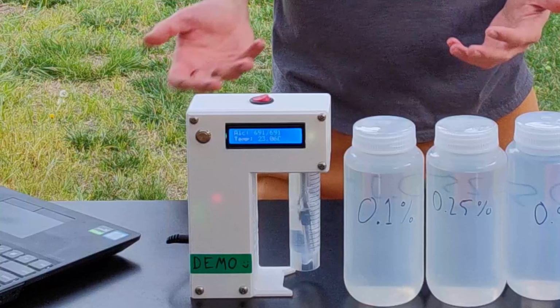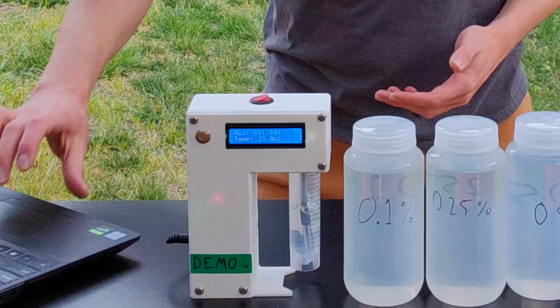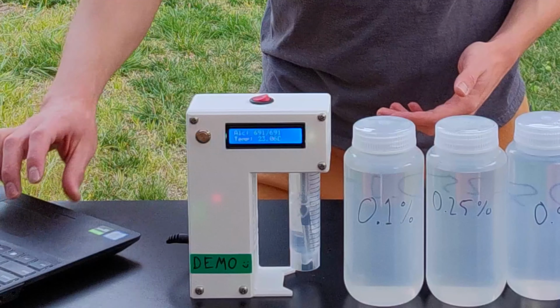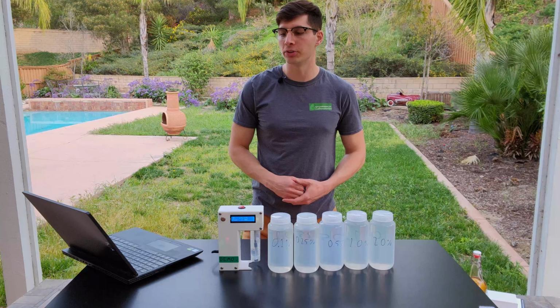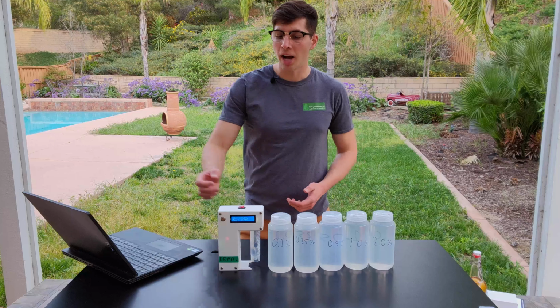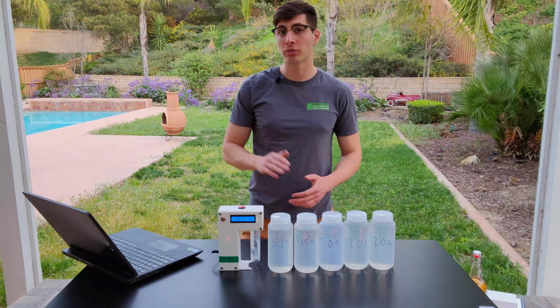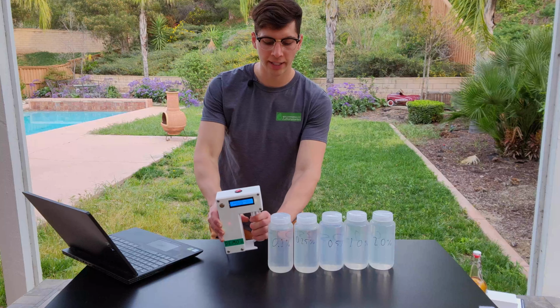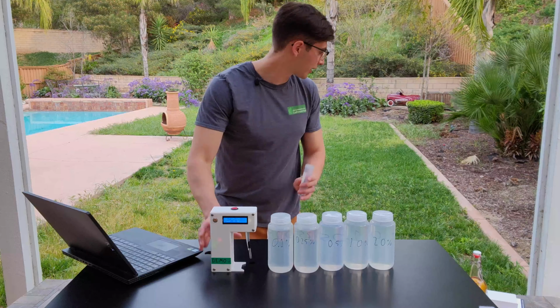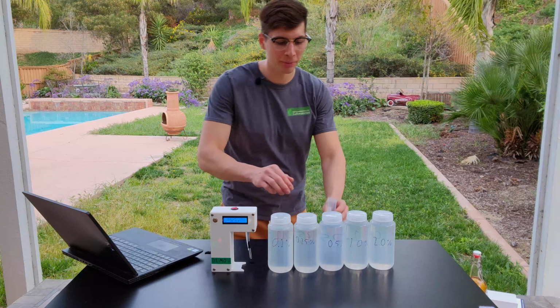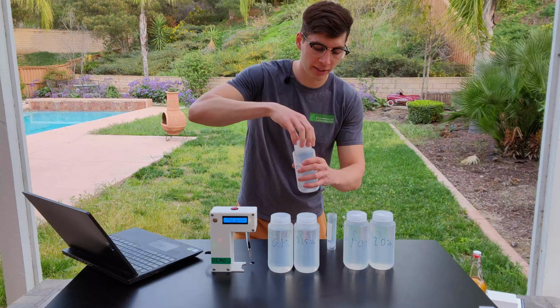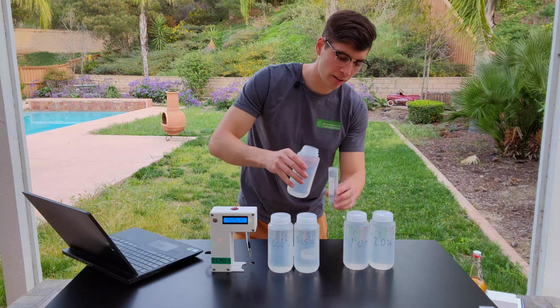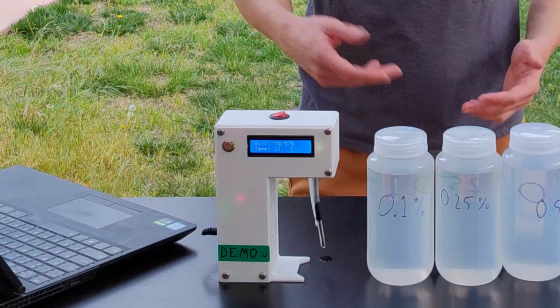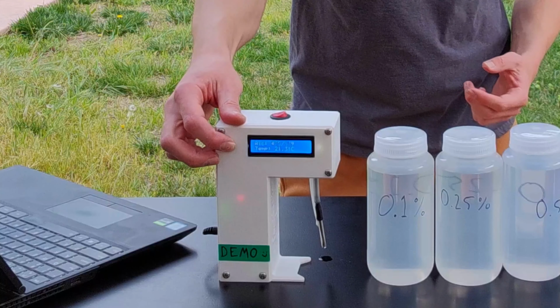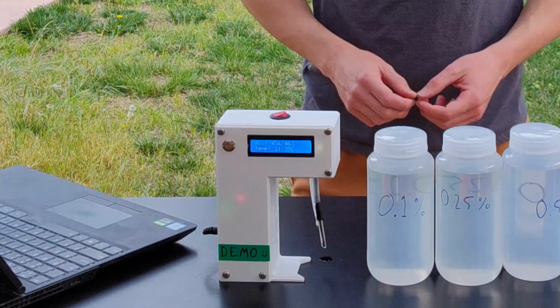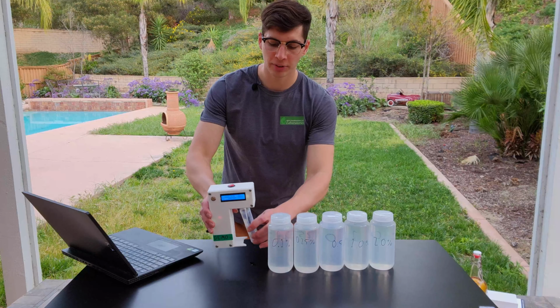So the readings seem pretty stable at about 690, so I'm going to enter that value into the Excel document in the position of the 0.25% alcohol percentage. I've also recorded the calibration temperature as about 23 degrees Celsius. All right, so we can take out this sample. Again, we don't reuse these samples, and I'll pour in the next 0.5% sample. The readings have fallen a significant amount, so I can press and hold the reset button on the left of the display. Now we can measure our 0.5% alcohol standard.